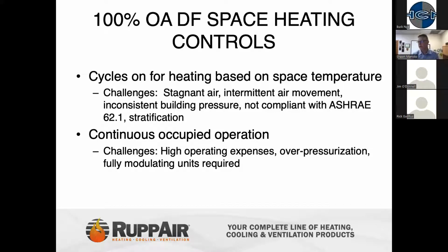In the case of having it continually operated in the occupied mode, the biggest challenge there is having high expenses. Always introducing that 100% outside air to the space that may not be needed. Maybe it's beyond the ventilation code requirements. Overpressurizing the space and making sure in this case here that you do have a system that was designed to do a full modulation type system. Preferably if it's going to be 100%, having not only modulating heat control, but also modulating blower control. So you can compensate for overpressurization and meeting minimum code requirements, not bringing too much air.